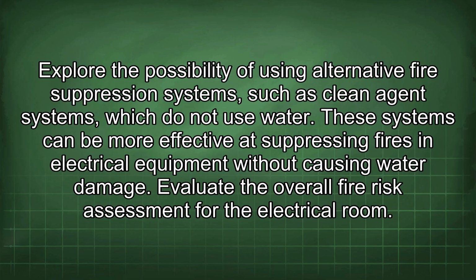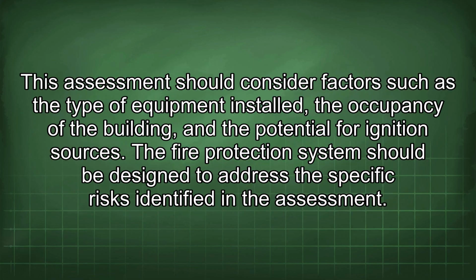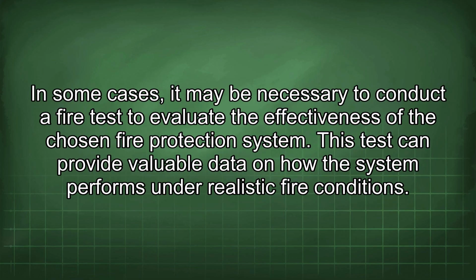Evaluate the overall fire risk assessment for the electrical room. This assessment should consider factors such as the type of equipment installed, the occupancy of the building, and the potential for ignition sources. The fire protection system should be designed to address the specific risks identified in the assessment. In some cases, it may be necessary to conduct a fire test to evaluate the effectiveness of the chosen fire protection system. This test can provide valuable data on how the system performs under realistic fire conditions.